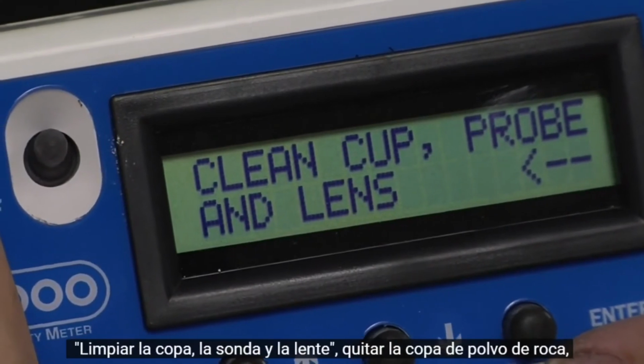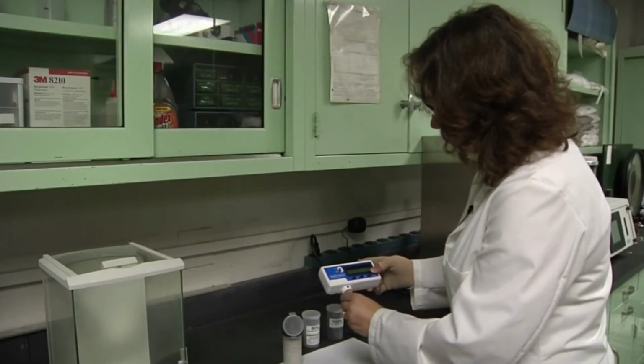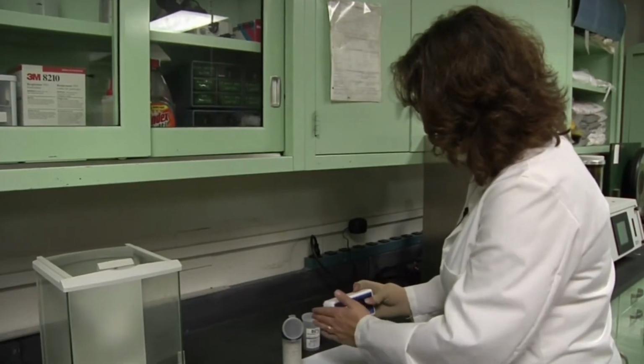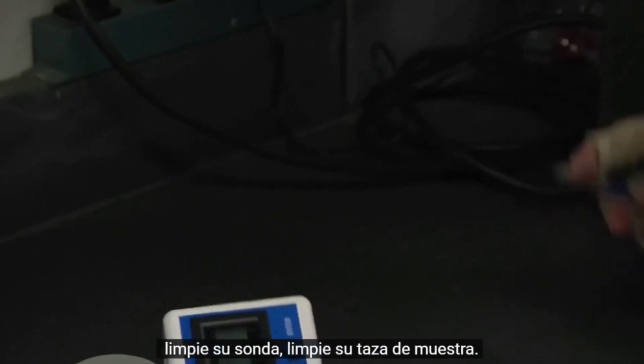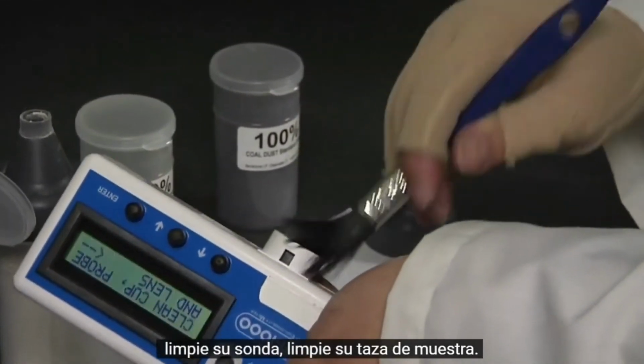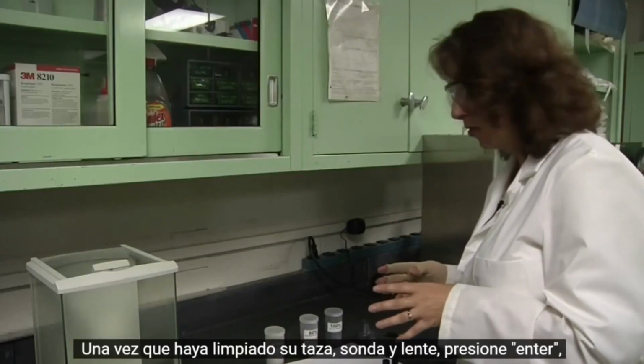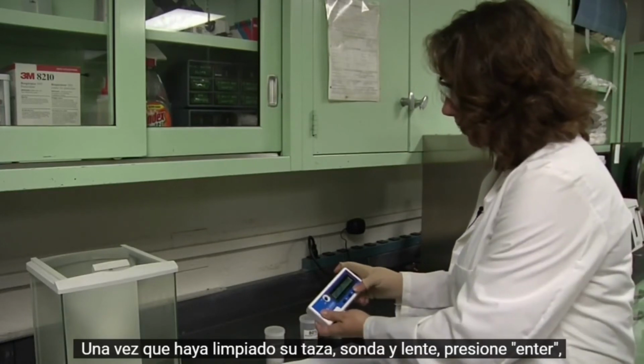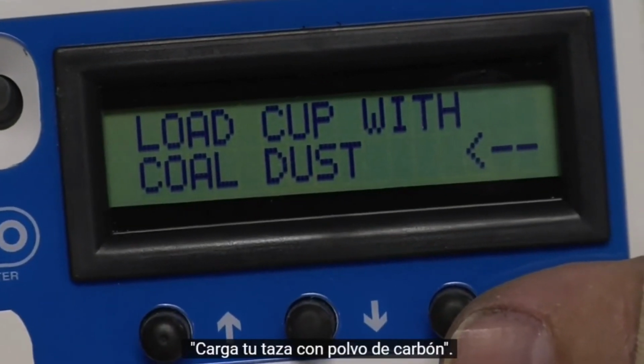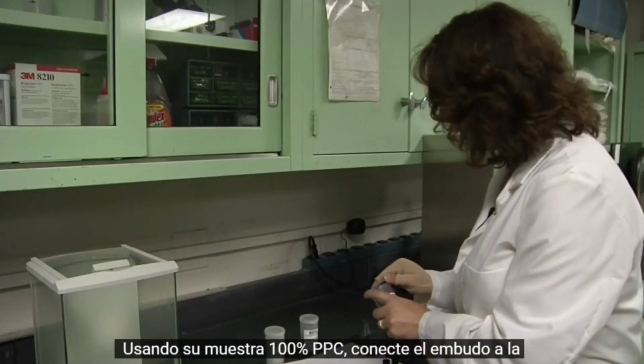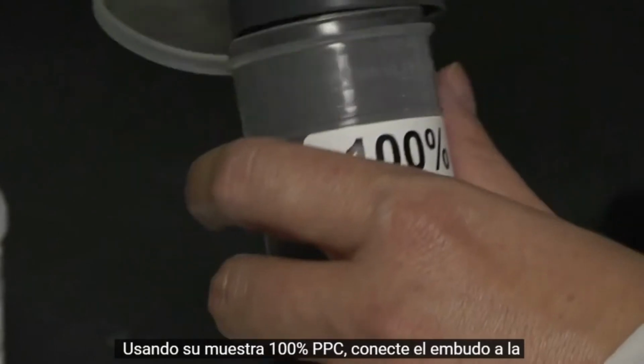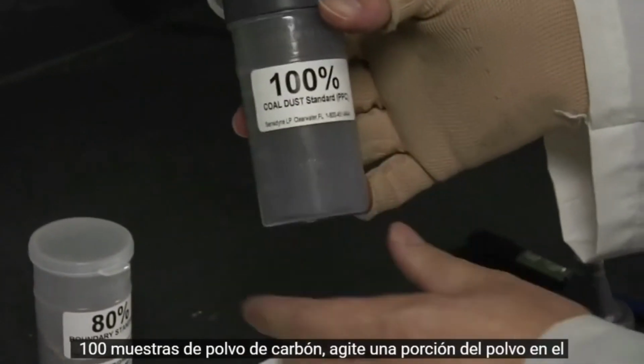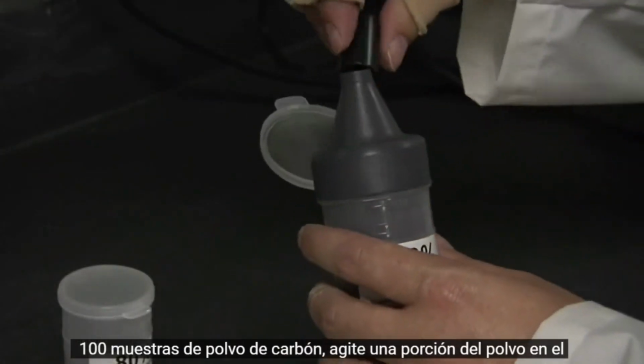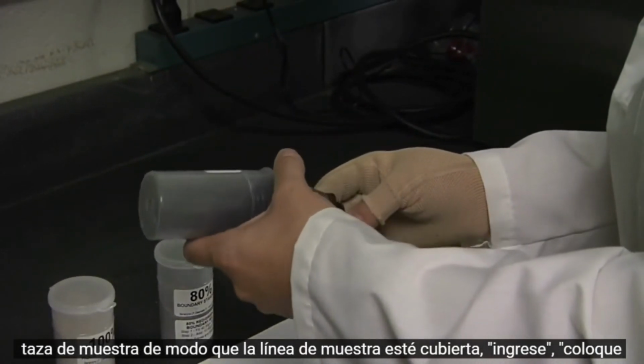Clean cup, probe, and lens. Remove the cup of rock dust. Clean your probe. Clean your sample cup out. Once you have cleaned your cup, probe, and lens, press enter. Load cup with coal dust using your 100% PPC sample. Attach the funnel to the 100% coal dust sample. Shake a portion of the dust into the sample cup so that the sample line is covered.